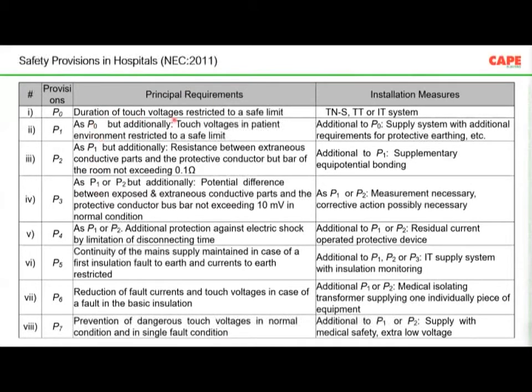P3. P0 means duration touch voltage restricted to a safe limit. This is by installation TNS, TT or IT system. But as I said, nowadays TT is not recommended. TNS is recommended for medical location. P1 is P0 plus touch voltage in the patient environment restricted to a safe limit. What does it mean? It means the touch voltage is lesser than 25 volt. P2, additionally, the touch voltage is reduced to less than 25 volt. Resistance between extraneous conductive parts and the protective bonding conductor bus bar of the room shall not exceed 0.1 ohm. Now, in the new standard, this has been modified to 0.2 ohm.